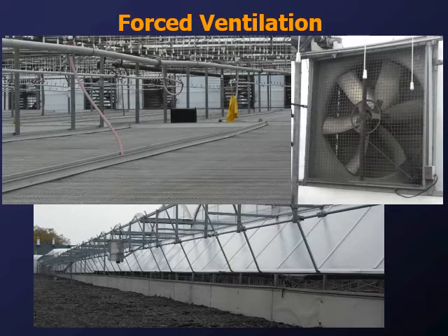Forced ventilation. This is with fans, exhaust fans. This is a typical fan. These are called ERM fans. They are set up in such a way that when the fan starts to turn, they spin some weights, and those weights act on a plunger, which then pushes the louvers open. So there's actually not a lot of moving electrical parts. There's just one motor to make the fan turn. They're very common in greenhouses now.